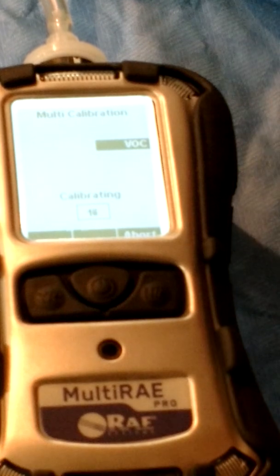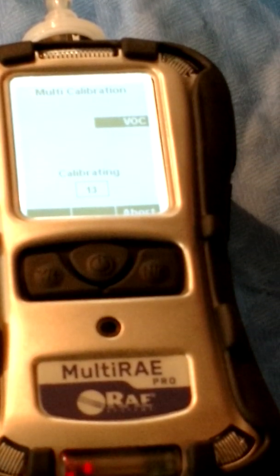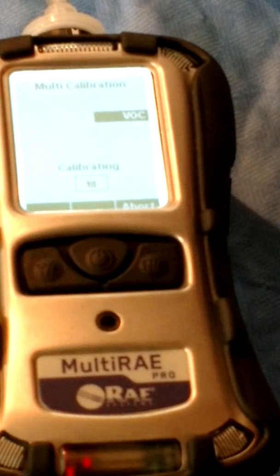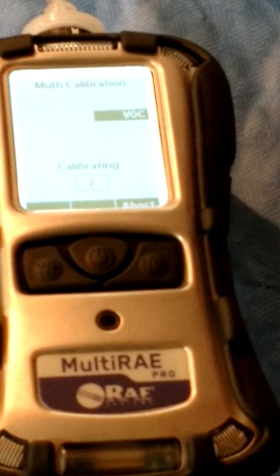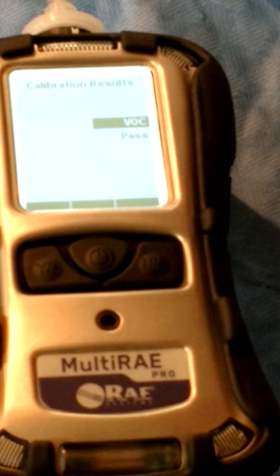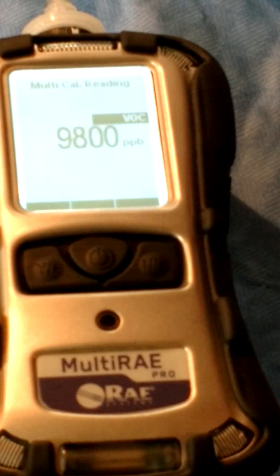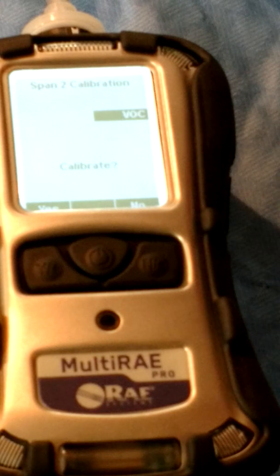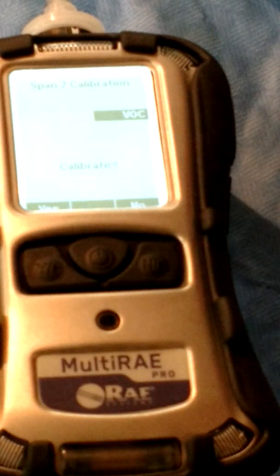Again, that's a 60-second calibration. Since the Multi-Rae Pro is a ppb meter, it differs from the Multi-Rae Lite in that this calibration is a 2-step process. The first step calibrates the VOC sensor at 10 ppm. Second part of the calibration will occur at 100 ppm. This is due to the large range of the sensor. In the Multi-Rae Lite, it is a 1-step process only at 100 ppm. So we had a successful calibration, and we'll move on to the second step.